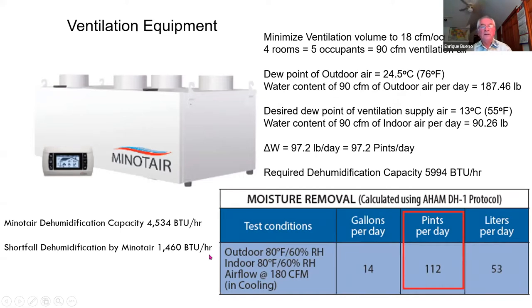Originally, we had designed the ventilation with a Ventacity ERV coupled with a Fujitsu DX coil for dehumidification, but the integration of the two became too complicated, and also didn't provide enough dehumidification, forcing us to have an additional dehumidifier inside, plus another mini split, cooling only.